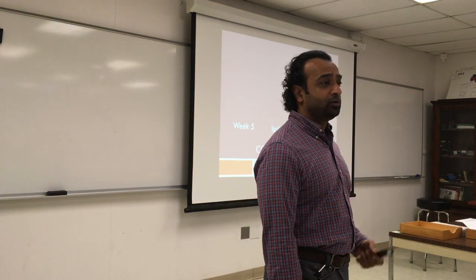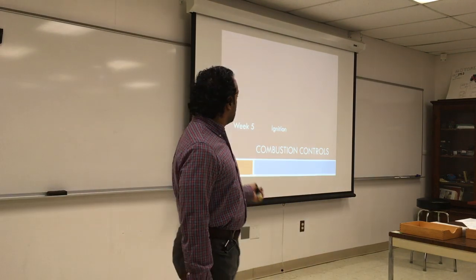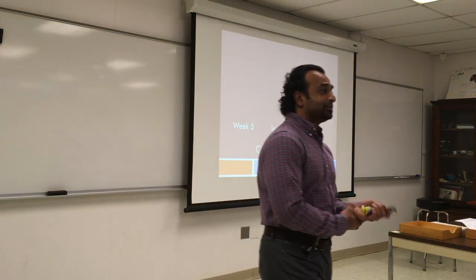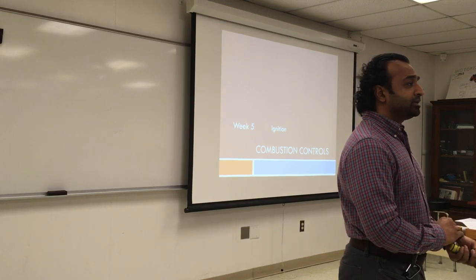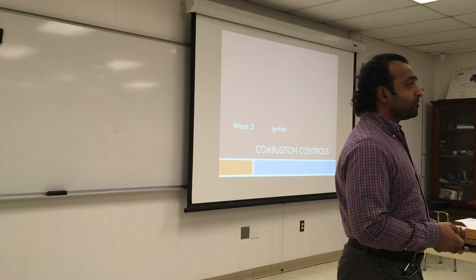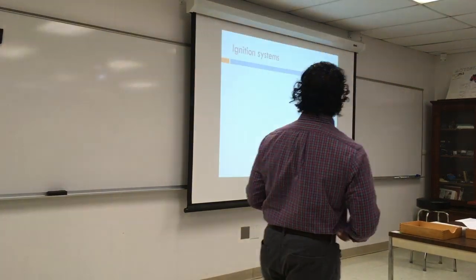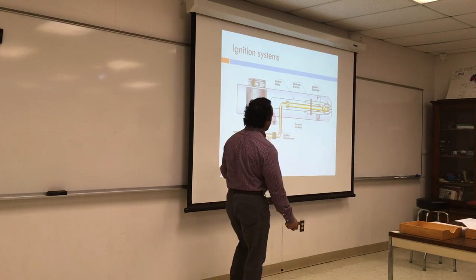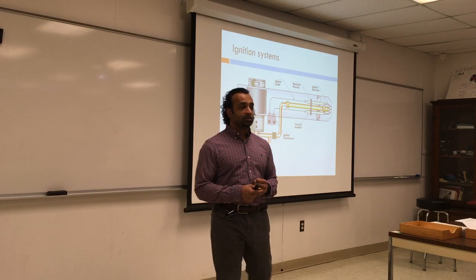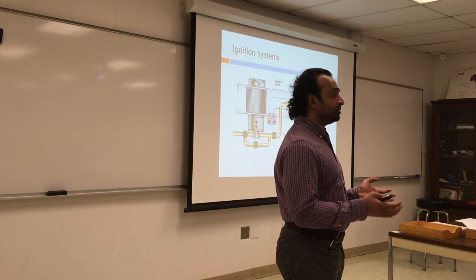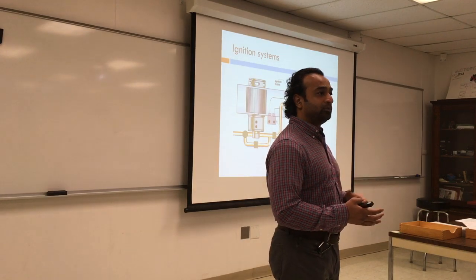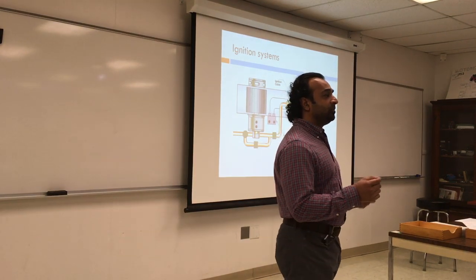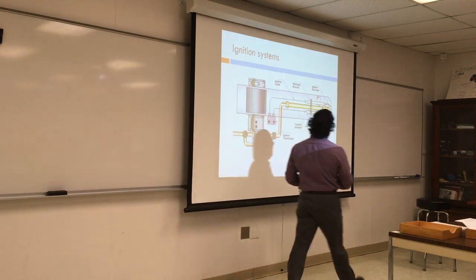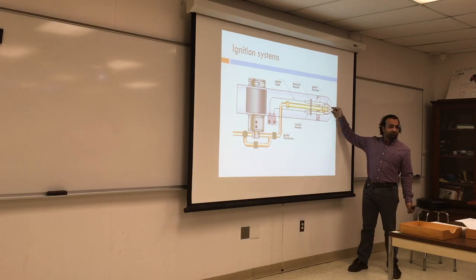Last week we're still finishing material because we backtracked a little bit. This material is a repetition of something we did already last semester, but it's good to know how it functions now when you don't go and work on your work. So we'll talk about the ignition system. We already talked about the nozzle distance, the spray angle, the density, and atomizing. Atomizing is very important because if you don't get the right density of droplets, it might not ignite. We talked about how we gap those nozzles from each other. Usually it's an eighth of an inch, but every manufacturer calibrates this distance based on the flow rate and the spray angle.